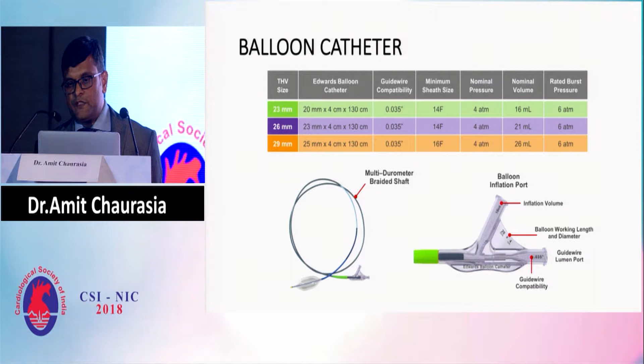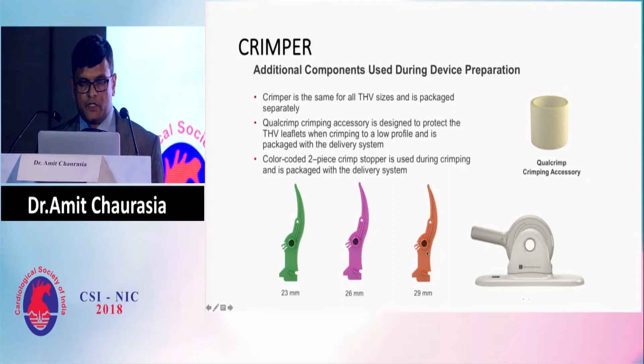Different volumes are needed for the inflation devices mentioned, and the nominal pressure is around 4 atmospheres, rated burst pressure is around 6 atmospheres. But the balloon expansion is a volume related thing, not a pressure related thing. The crimper comes with a Qualcrimp accessory device which actually protects the valve leaflet while you are crimping, and it prevents damage. It also comes with a different color coded stopper so that you can actually crimp the valve. This is the inflation device. For 23 and 26 millimeter you have a pressure monitor, but not for 29 millimeter, and this is a volume based inflation. It's not a pressure based inflation that you keep on seeing out there.